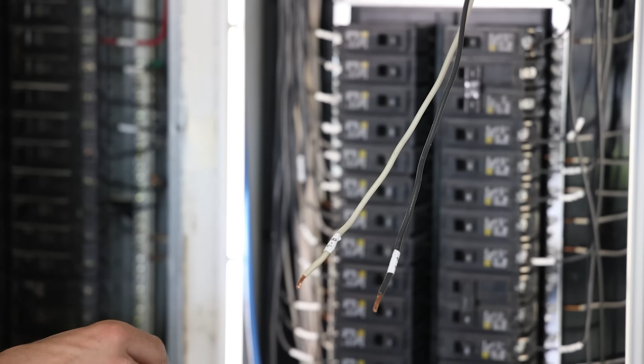Here's a little pro tip. If a breaker trips, it goes to that middle position. If it's a square D QO, it's got a little red flag. Sometimes, I'm talking like 2 times in 100, it won't actually go to the trip position. It'll be internally tripped, but the handle is still in the on position. So if you think you got a power outage in the house, you're not sure, run your finger lightly down the breakers like this, and if it is tripped, it'll pop right over and you'll see it. Aha, I just prevented you a $205 service call. You can thank me later.